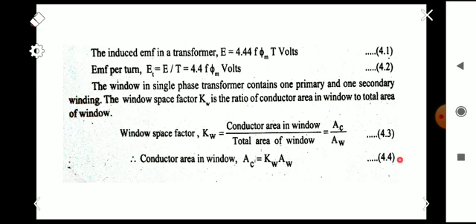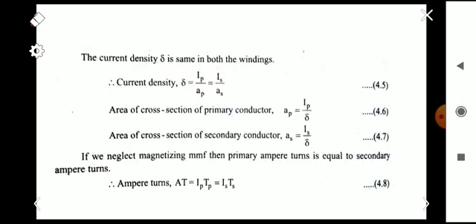The current density δ is the same for the primary and secondary winding. That is, δ = I_p / A_p on the primary side, and δ = I_s / A_s on the secondary side, where I_p is the primary current, I_s is the secondary current, A_p is the cross-sectional area of the primary conductor, and A_s is the cross-sectional area of the secondary conductor. From these equations, A_p = I_p / δ and A_s = I_s / δ.